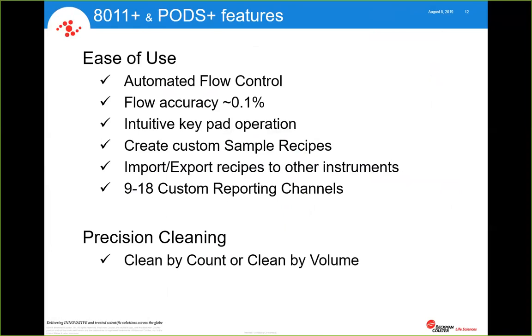The new 8011+ and PODS+ have automated flow control. There's no readjustment of pressure regulators to accommodate thinner or thicker fluids. The flow accuracy is around 0.1%, very, very solid. Again, intuitive keypad operation, and the user interface is very simple. You can create custom sample recipes, and you can create custom reporting standards. So if the canned reporting standards available with the instrument when you buy it, like ISO 4406 or NAS or SAE or NAVAIR or GOST, and I think there's an ASTM standard in there, don't fit your needs...